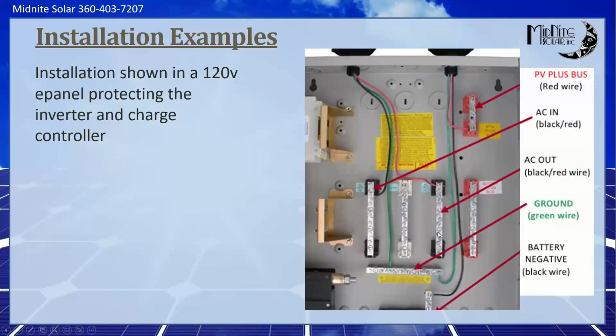Here's an example of one being installed in a 120 volt E panel. So if you've got an Outback FX, a Magnum MS, a Samlex, a Little Rosie, you have 120 volts, so you don't have the second leg. So you use a single SPD 300 AC. Use the black on the AC in and the red on the AC out. You can use either color, either place. They're interchangeable. But you protect the AC in and the AC out with a singular SPD. So that's a bonus. You get to use one.